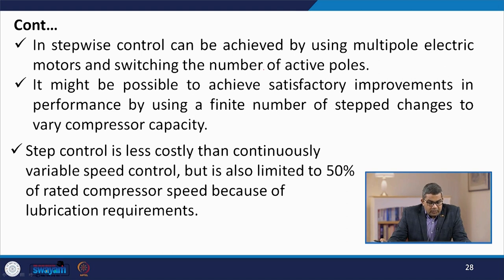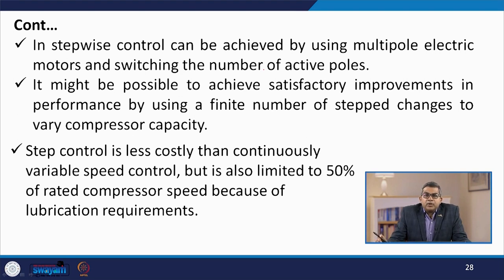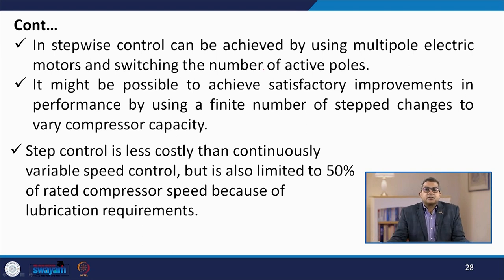Step control can be achieved by using a multipole electric motor and switching the number of active poles. It may be possible to achieve satisfactory performance improvement using a finite number of step changes to vary compressor capacity. Step control is less costly than continuous variable speed control, but is also limited to 50% of rated compressor speed due to lubrication requirements.